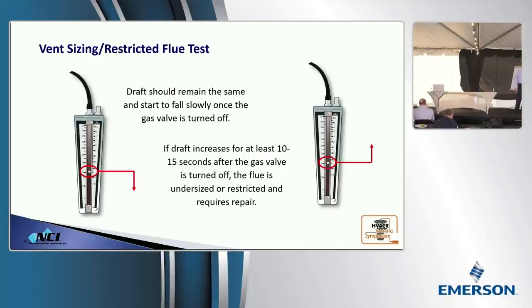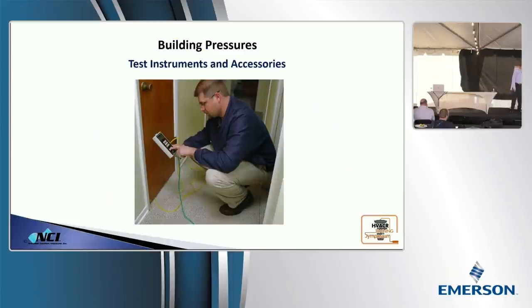If the draft all of a sudden, after about 15 seconds, shoots up, that flue is restricted, because you're taking away the heat from that flue gas. It almost acts like a pressure relief, and you'll watch that ball in that draft gauge shoot up. That means you need to start looking at the flue sizing. And here's what's scary: guys run into this on systems where they just installed a flue liner. Flue liners are flex duct for flue gas. Do flex ducts move more air than hard pipe? No, the same principles apply to flue gases as well.